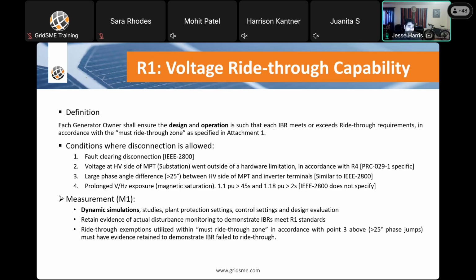So how do we measure this? How do we show this? How do we prove that we're in accordance with requirement R1? Dynamic simulation studies, plant protection settings, control settings, and design evaluation are all used to prove that design portion of the definition. And then as far as the operation portion goes, you need to retain evidence of actual disturbance monitoring to demonstrate that IBRs meet R1 standards.